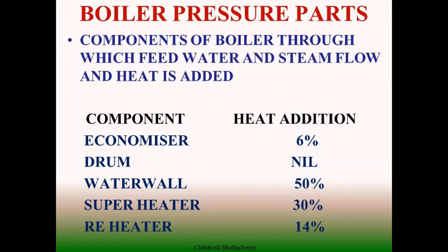Then maximum heat transfer is taking place in the water walls, which are encasing the furnace and receiving the maximum amount of radiant heat. Then around 30% heat is absorbed by superheaters, and around 14% heat is absorbed by reheaters.